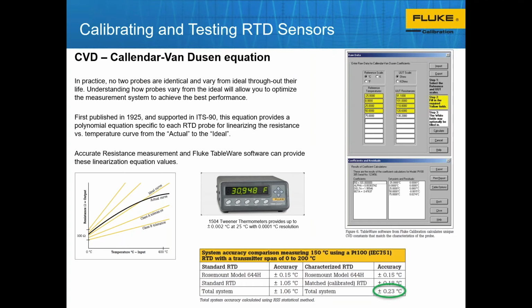So what I'm saying here is that if we know the actual resistance output values of our test points, we can use this and go through some calculation in a software we have called TableWare. And it gives us these type of improvements in the bottom of the presentation here. So you may be running with a Rosemount transmitter, that's their advertised specification.